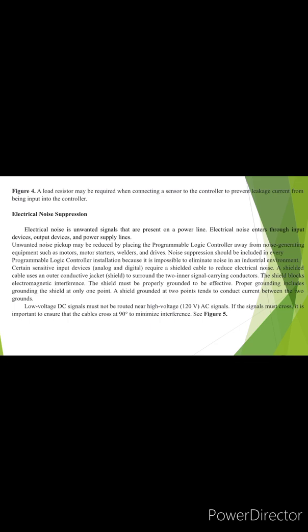Certain sensitive input devices, analog and digital, require a shielded cable to reduce electrical noise. A shielded cable uses an outer conductive jacket shield to surround the two inner signal-carrying conductors. The shield blocks electromagnetic interference. The shield must be properly grounded. To be effective, proper grounding includes grounding the shield at only one point. A shield grounded at 2 points tends to conduct current between the two grounds.